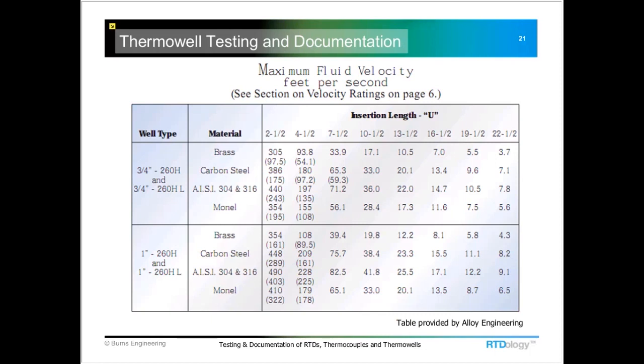Some of the manufacturers, this one happens to be from Alloy Engineering, publish a little table with some conservative values that will give you a rough ballpark idea of what an acceptable fluid velocity is based on the immersion length. So we've got the immersion length up here. If we look at 4.5 inches, and let's say we've got a 316 stainless well, it's showing 197 feet per second fluid velocity. And I think the ones in parentheses here are, actually 197 is probably steam and this is fluid, I don't quite remember.